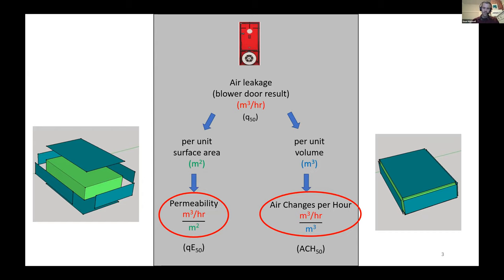The thing is that when talking with a lot of people, say homeowners, talking about air changes per hour is a little easier to relate to for everyday people who don't need to know much about this. It's a good thing that permeability and air changes per hour are pretty similar, because with air changes per hour, it's a little easier to relate to someone. If you said, in this room, all the air is going to leave one time in 1 hour, that's one air change per hour. And people can sort of get that. But if you said, all right, let me visualize 1 cubic meter per hour of air leakage going through every square meter of envelope area, this enclosure here, that's just not that easy to relate to. So it's convenient that for houses, they're pretty similar.